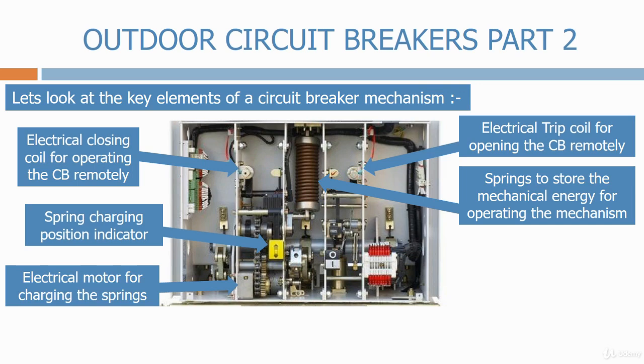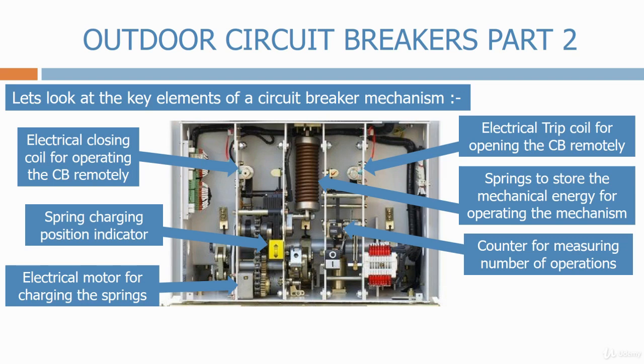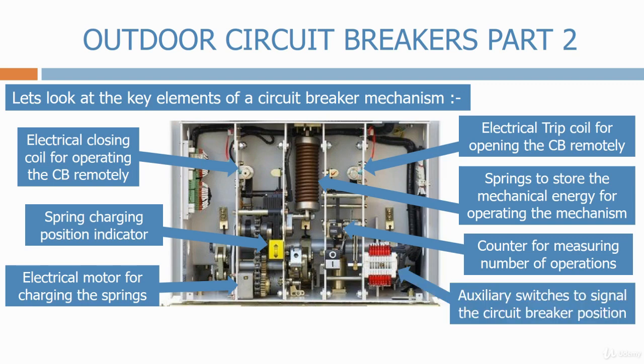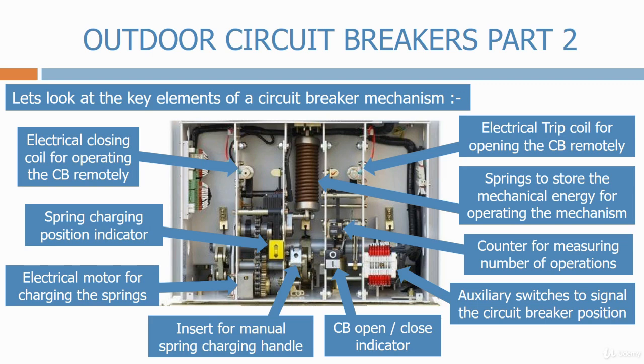This can either be an AC motor or a DC motor. We have the counter for measuring the number of operations. This is important information for maintenance. We have the auxiliary switches to signal the circuit breaker position. These are connected to the same shaft that drives the circuit breaker contacts. We have the circuit breaker open or close indicator, which indicates the position of the circuit breaker. And finally, we have the insert for the manual spring charging handle. This is there in case we lose all power to the circuit breaker and need to charge the mechanism manually.